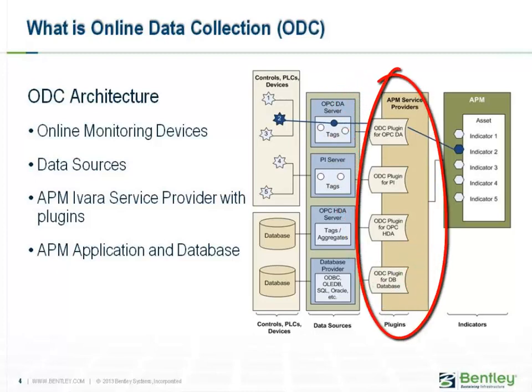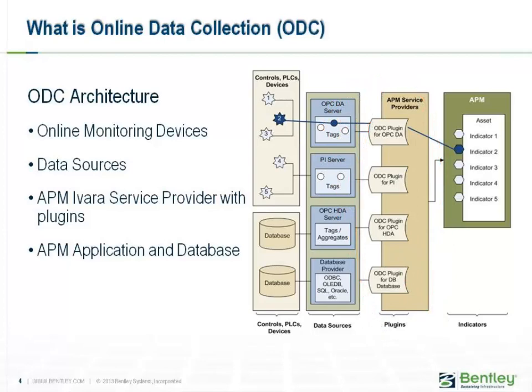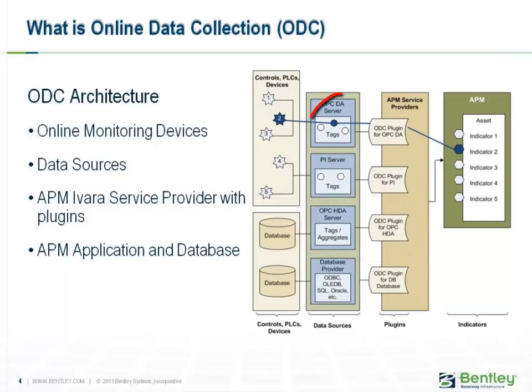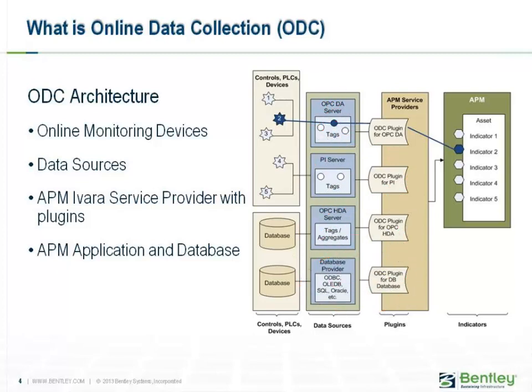The APM service provider is the component responsible for communicating with data sources through plugins. The provider has one specific plugin for each data source type: an ODC plugin for OPC DA server, an ODC plugin for OPC HDA server, an ODC plugin for PI Process Historian, and an ODC plugin for databases. Additionally, Bentley can provide a custom plugin to collect data from a custom data source using an Application Programming Interface (API).